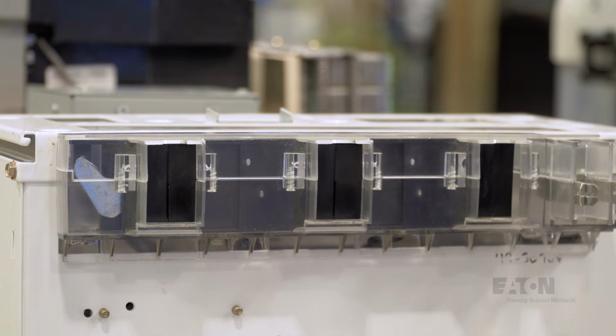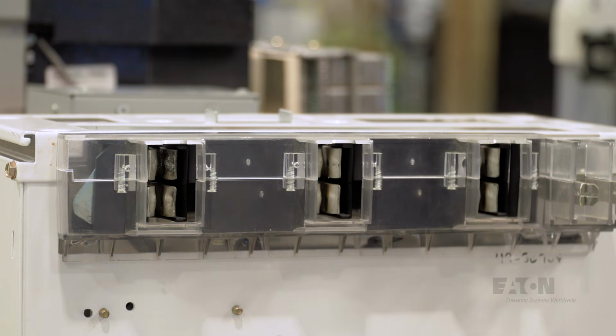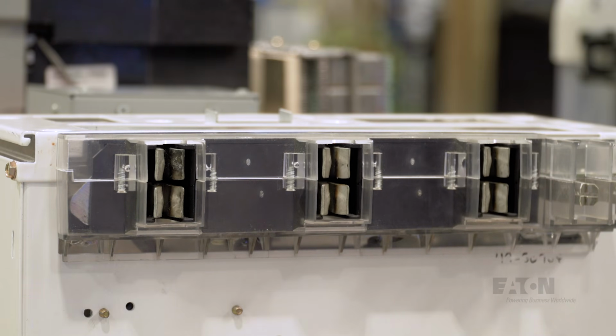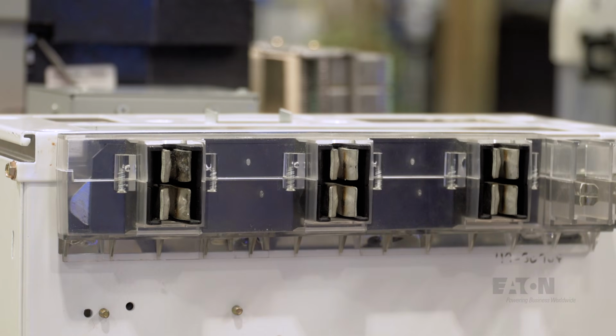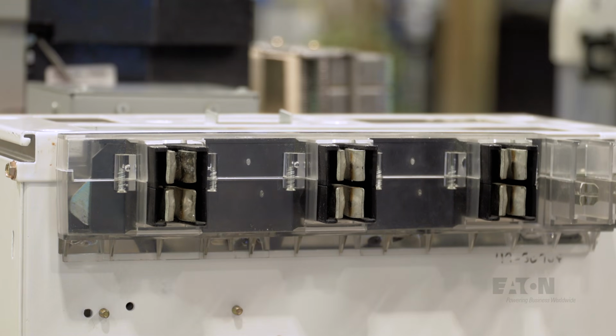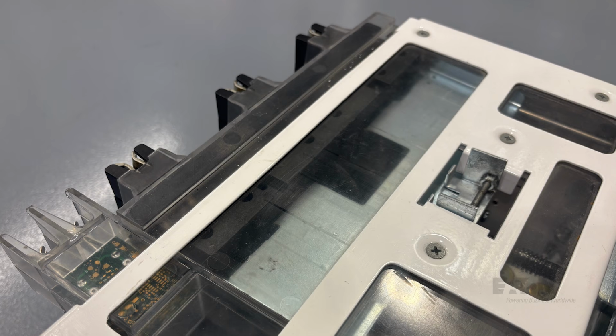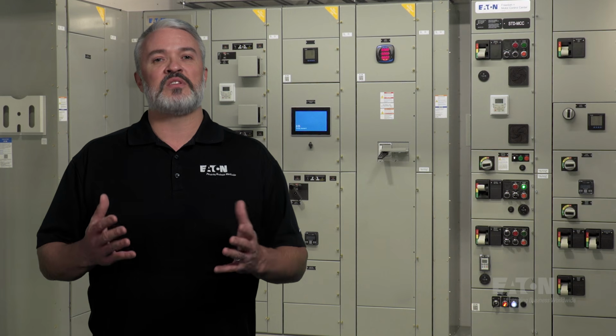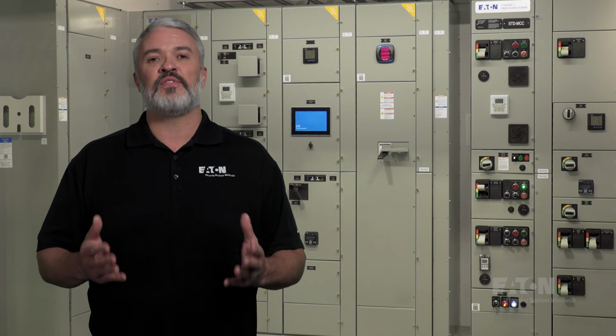Tin-plated copper alloy self-aligning stabs are mounted in a glass reinforced plastic insulation block that totally shrouds each stab and ensures positive alignment of the stabs with the vertical bus. The insulation block is also an integral part of the phase-to-phase isolation system. The power wiring is welded to the stabs and is totally contained within the unit enclosure, which means the vertical bus compartment is completely free of wiring for safety and reliability.